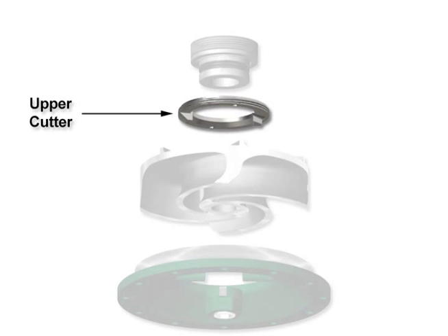The upper cutter provides added protection to the mechanical seal area by cutting against the inside diameter of the pump out vanes. Solids that could normally pack around the seal and damage the seal faces are further chopped and pumped away by the upper cutter.